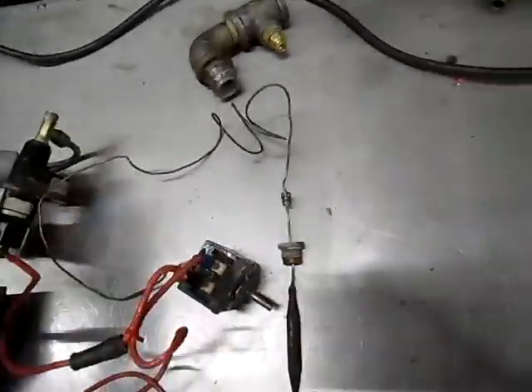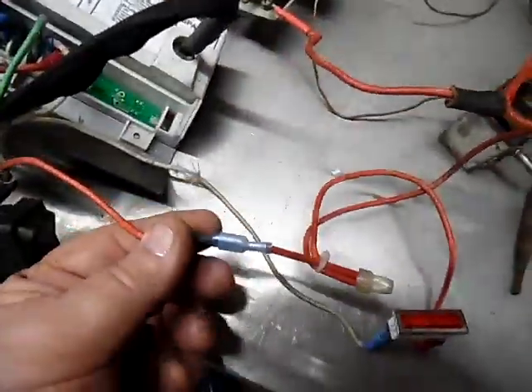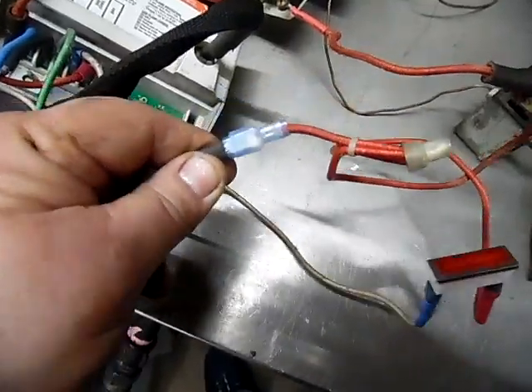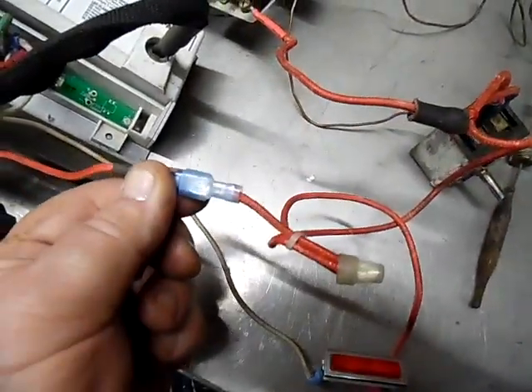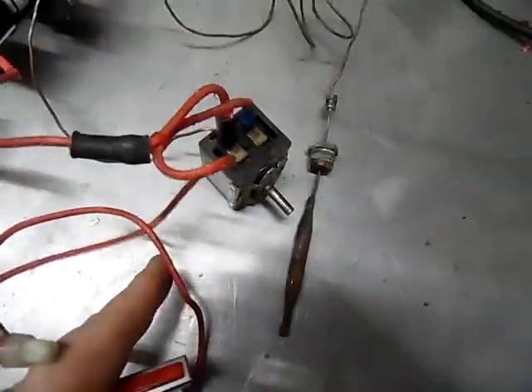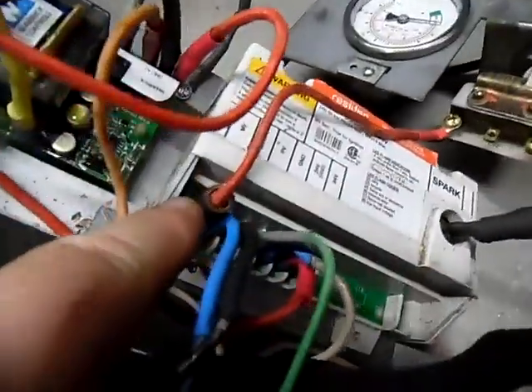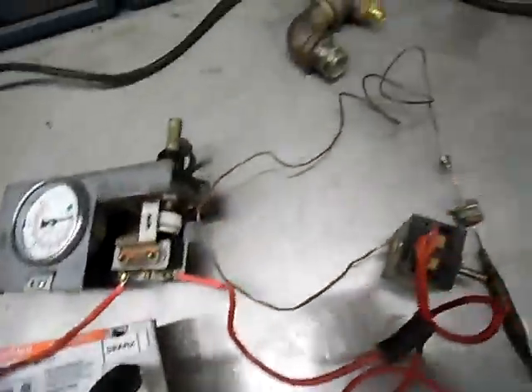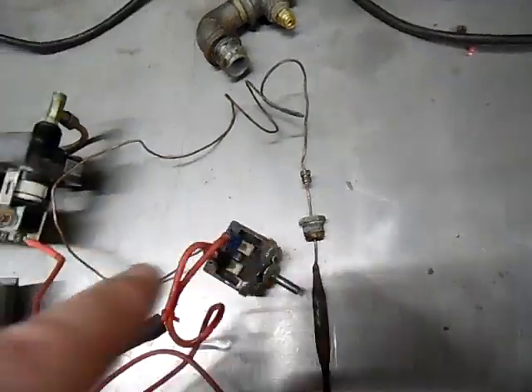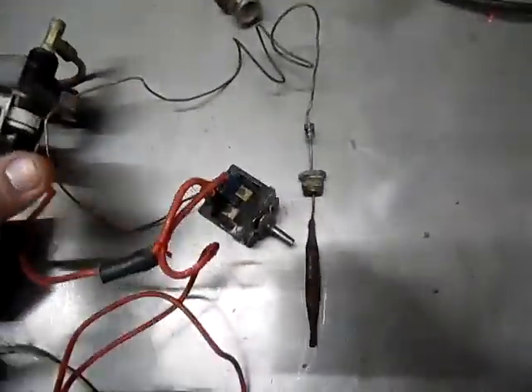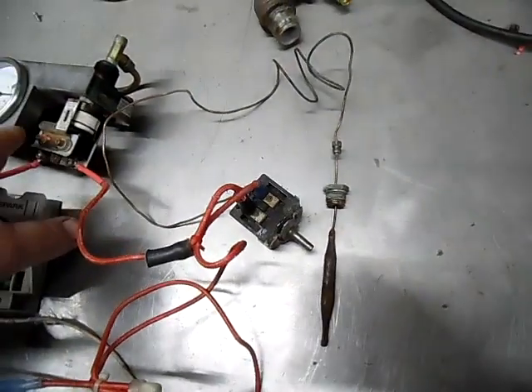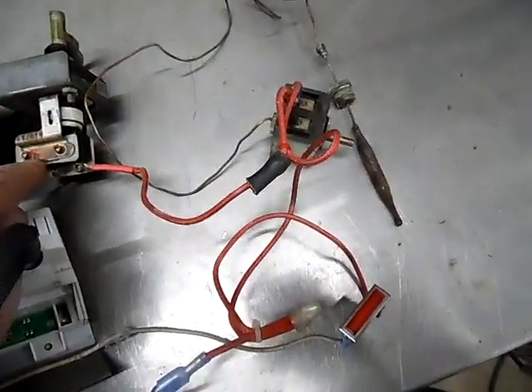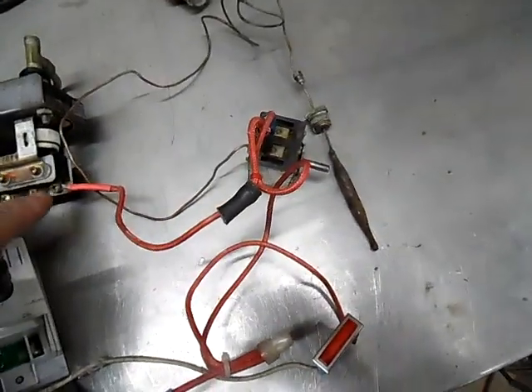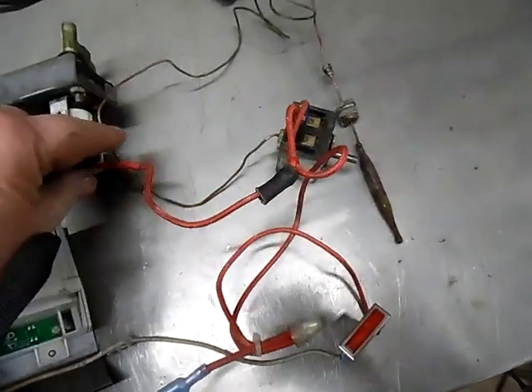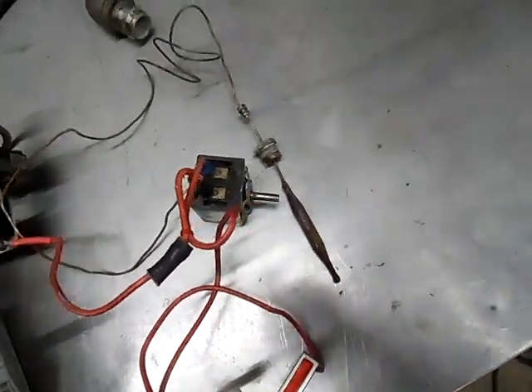Quick way to test your two components, we put a jumper in between ours here. This is the wire going directly to MV on the gas valve. It's at the end of the trail. If you were to hook this right to here and take your MV off, we have bypassed the pressure switch and the thermostat. If our system fires up and works properly, then we're going to be looking at these two components. And sometimes these can act up, meaning they'll work, won't work. Put your meters on them. Jiggle the wires. Let it run a minute and see if you drop voltage out.